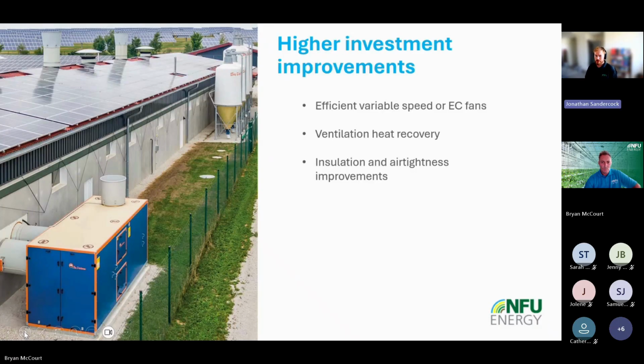Moving on to some of the higher investment improvements. The first major opportunity is often ventilation systems, especially with the heat that we've been having. Upgrading fans to the likes of EC fans, so that's electronically commutated fans, permanent magnet fans, or highly efficient AC fans with variable speed controllers. They're all commonly available technologies. Which one you use is generally less important than the rated kilowatt hour per volume of air delivered.